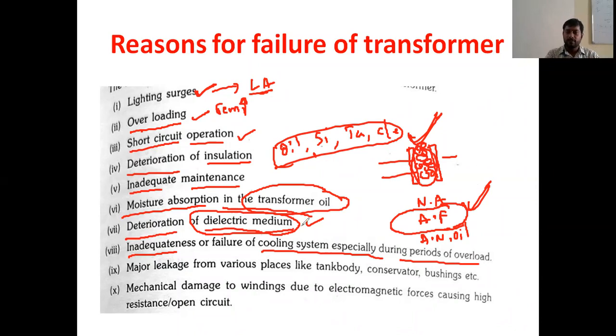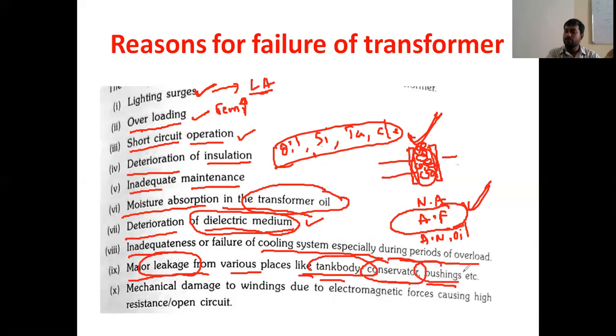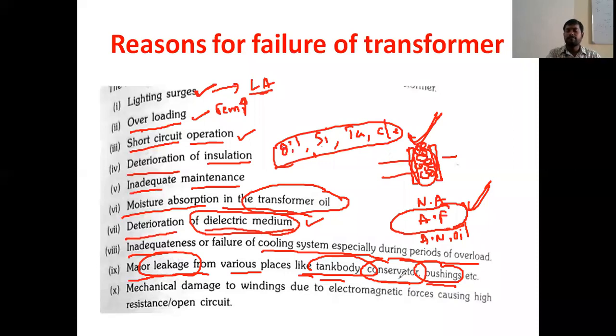Major leakage from various places — such as the tank body, conservator tank, and bushings — is also a cause. If oil leakage takes place, then the temperature absorption from the winding will be reduced, so the temperature of the winding will increase. Because of that problem, the transformer will get burned.